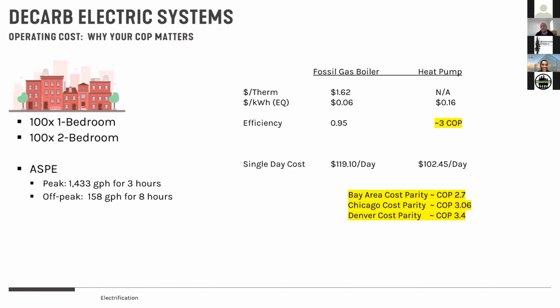If I move that same project to Chicago based on their utility rates, I actually need to get quite a bit higher. I need to hit 3.06 before I even break even on an operating cost standpoint. If I go to Denver, it gets even worse. So colder climates and their utility rates heavily bias gas, even more so than California. And so now I need to get to a COP of 3.4 during the full range of operating, averaged out to 3.4, in order to hit cost parity. And that's really important because COP is driven by my design conditions. And when I move to cold climates, those design conditions get far more challenging than, say, Central Valley, California, or especially coastal California.